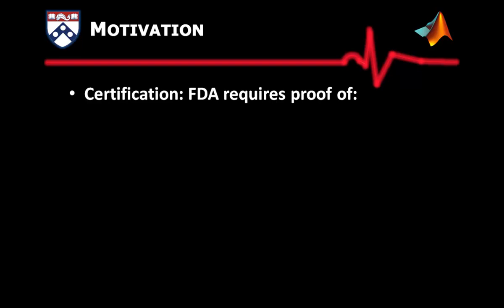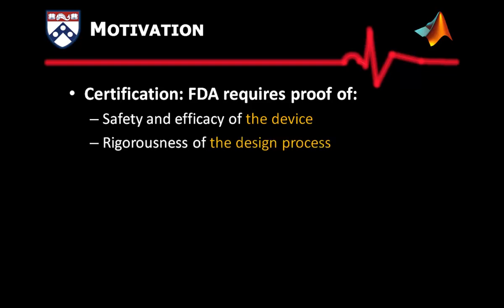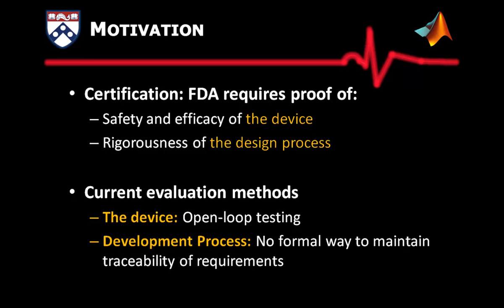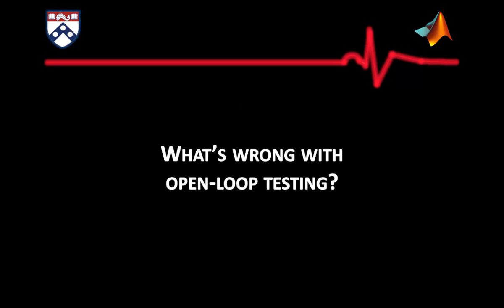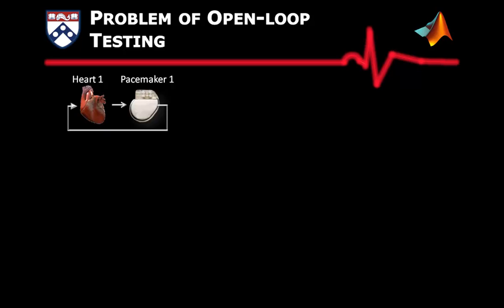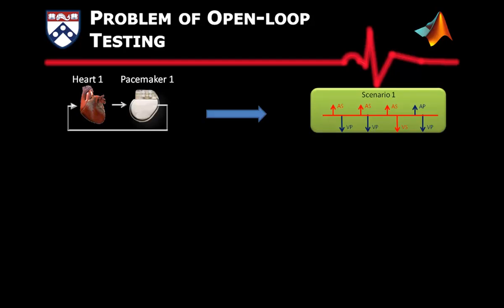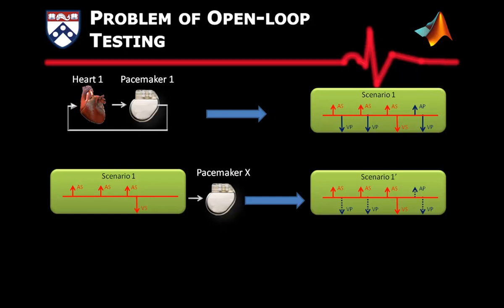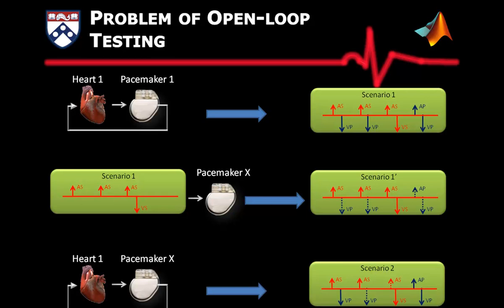During pre-market device certification, the FDA requires proof for both the safety and efficacy of the device itself and the rigorousness of the design process. Currently, the state-of-the-art evaluation method for the device is open-loop testing, and there is no formal way to maintain the traceability of requirements during the development process. Our motivation for this project is to identify the problems with this evaluation method and how we can improve during model-based design. When a new pacemaker is being developed, manufacturers replay heart signals from closed-loop scenarios into the new pacemaker and compare its output to the original outputs. However, the new pacemaker may have different outputs which can change the state of the heart — open-loop testing does not cover these aspects.